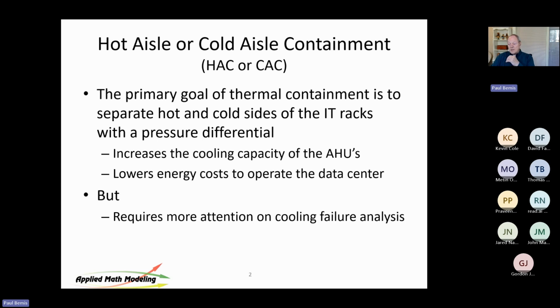That's where it starts. And as a result, it has an effect on things like N+1, because when you contain like that, it's really great thermodynamically. But if you have a failure, you now have a pressure variation, because you're trying to blow air into a high pressure environment if the cooling units are down and it's contained, for example, on hot, or vice versa on cold. So it's important to make sure that you understand what happens in a failure mode situation.